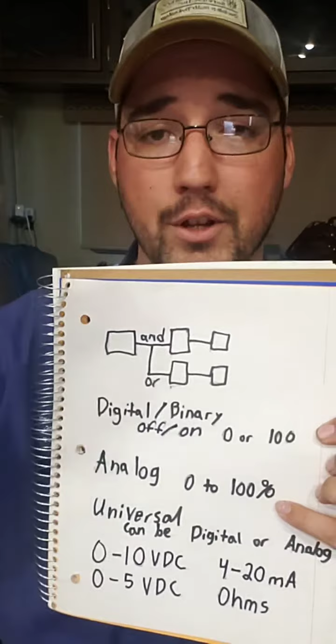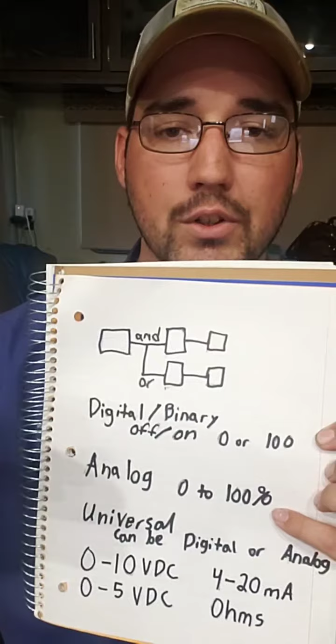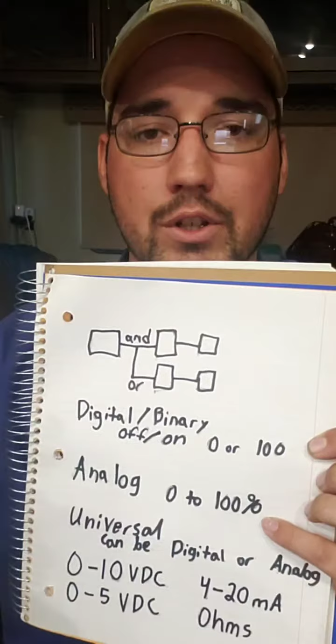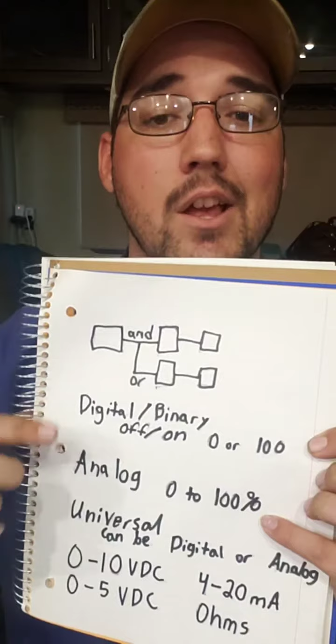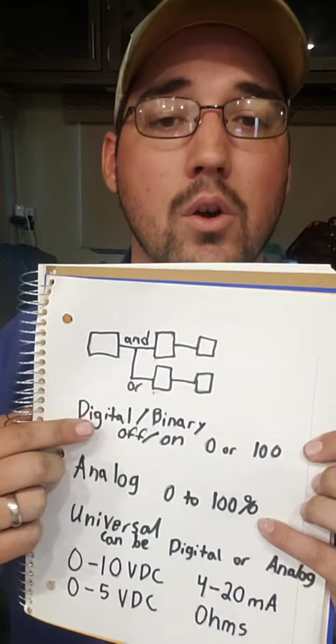A binary input would be a low pressure switch, a high pressure switch. If we're dealing with a furnace of any kind, you could throw in high limits. Anything that is either off or on, any switch that opens or closes, or a coil. If you're needing to energize a coil, that is a binary device. Contactors, relays, safety switches in general, fan proving switches if you deal with a lot of VAV equipment or fan power boxes. All those are binary devices. They're going to be hooked up to the board on the DOs or BOs depending on what your board is.